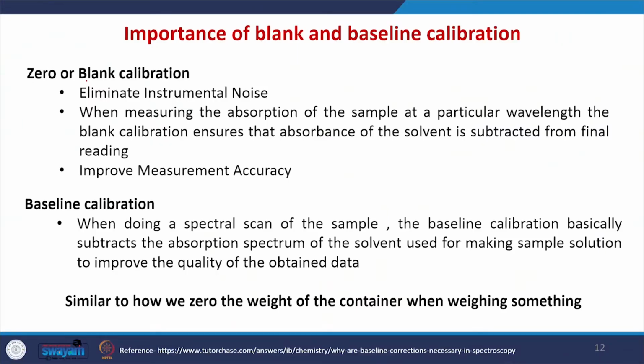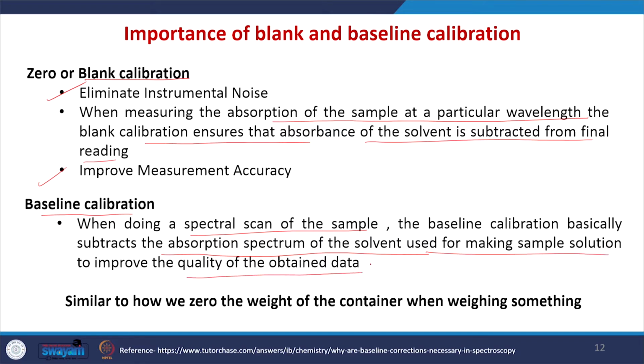Let us learn about the importance of blank and baseline calibration. The blank calibration eliminates the instrumental noise, and when we measure the absorption of the sample at a particular wavelength, the blank calibration ensures that the absorbance of the solvent is subtracted from the final reading, and this way it improves the measurement accuracy. The next one is baseline calibration. When we do the spectral scan of the sample, the baseline calibration subtracts the absorption spectrum of the solvent used for making the sample solution to improve the quality of the obtained data.